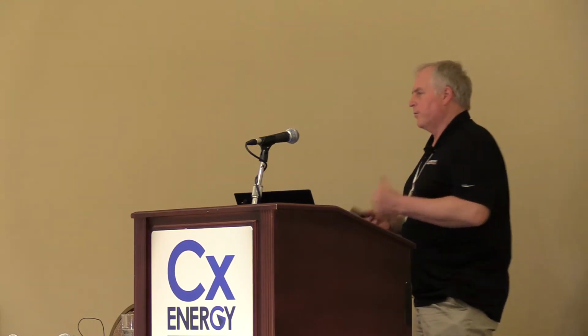So when you start talking about what the objectives are, you have to remember that energy efficiency is very important, but again, you also have to understand that you don't want to jeopardize production or any operations, including building comfort. So again, we're going to talk about the trim, varying loads that you're going to want to run. For multiple compressors, you're going to want to look at sequencers, especially for any large compressors. You want to be able to do sequencing, turning the compressors on and off on demand.